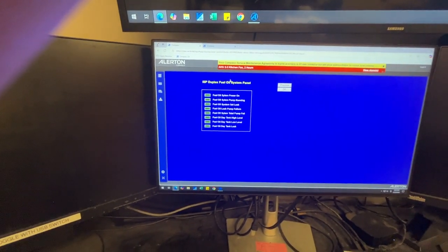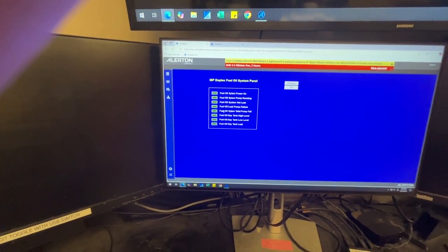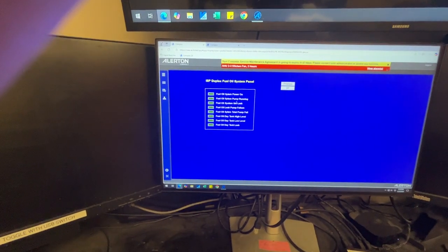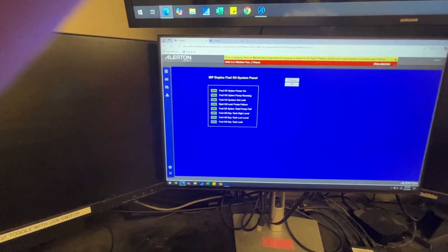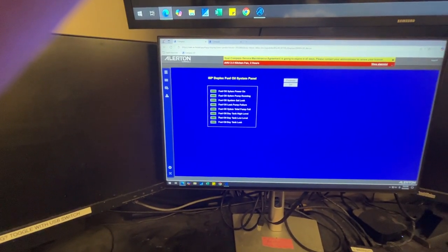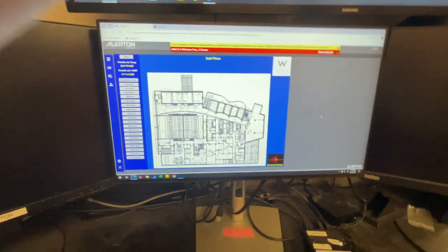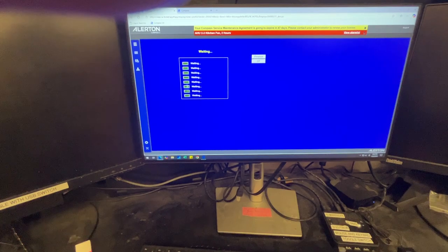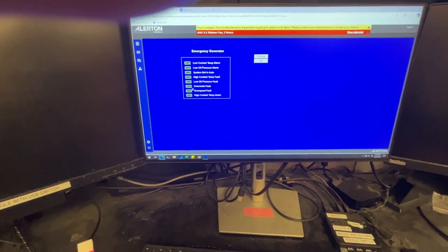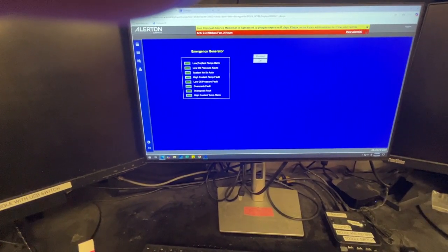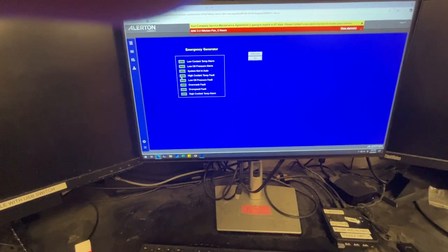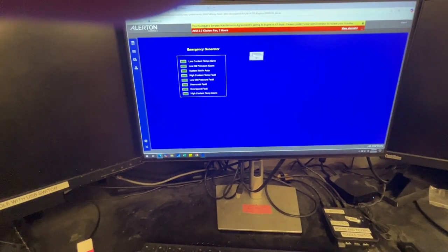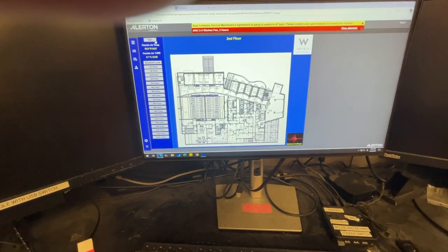There's a fuel system on there that has like an overflow tank. So if it does start to leak, high level, low level, it will throw alarms here. Same with the generator. The generator point list will also land here. There's overspeed, high coolant. Anytime something is wrong, it will send an alert to the BMS system.